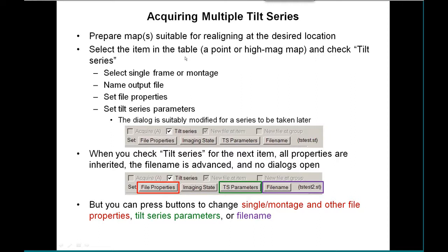The next step is to select an item in the table that you want to acquire the tilt series at — which could be a point or a high mag map (the latter is recommended) — and then check tilt series. When you check that, it brings up a series of dialogs: first a simple one to select whether it's a single frame or montage, then you pick the output file, then you enter your standard file properties menu for picking the data type and header properties, and then you enter the tilt series parameter dialog — the same old dialog you've seen for tilt series, but modified slightly to account for the fact that this is for a series to be taken later, so some options are not active.